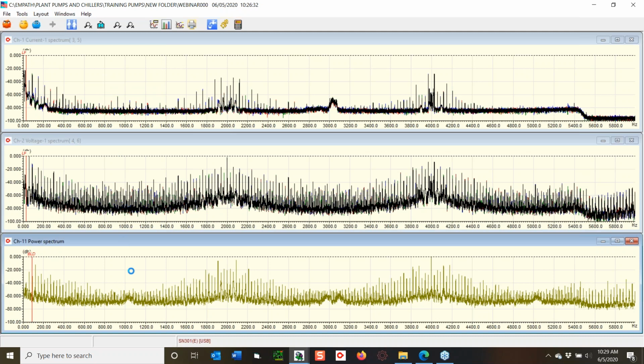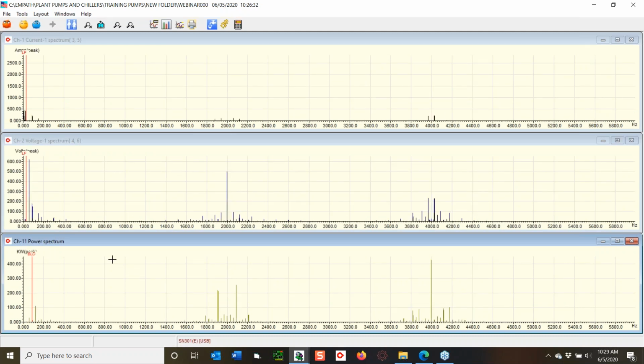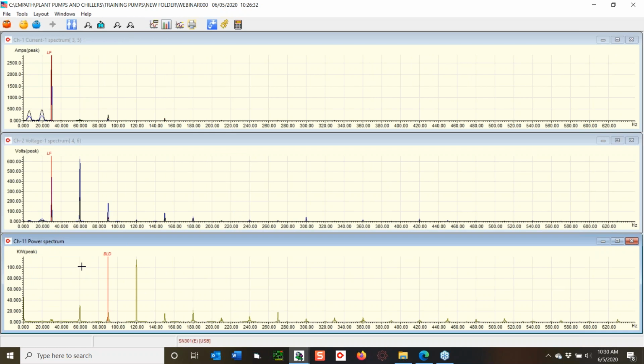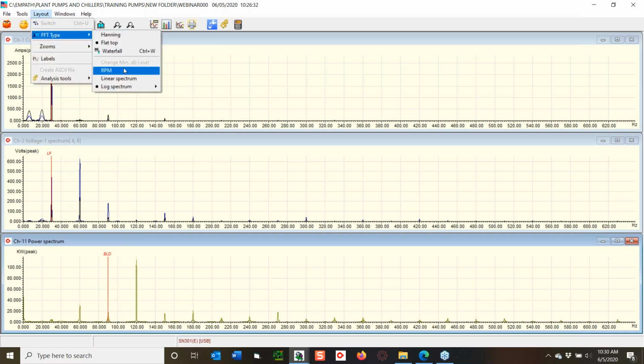What this does for me when I'm analyzing down here is it gives me absolute values. So if I come in here and I'm looking at it, also, like I said, it also changes that up here to current. But if I see a specific issue, I can come in. So blade, if this was a blade frequency here, its value is about 16 kilowatts worth of energy. That would be a defect if that was actually it. So in any case, that's one of the things I can do there.